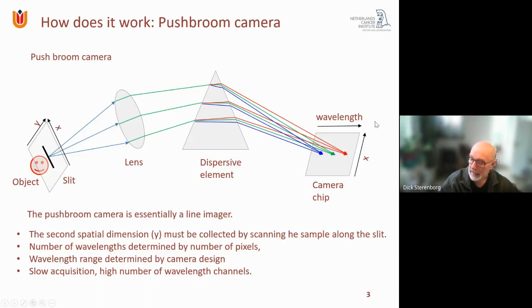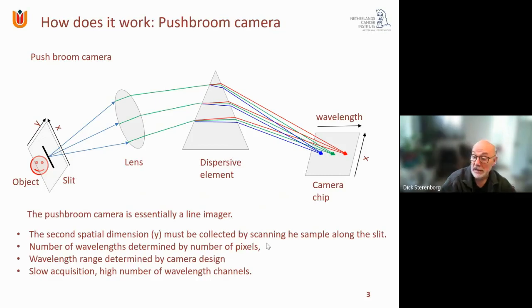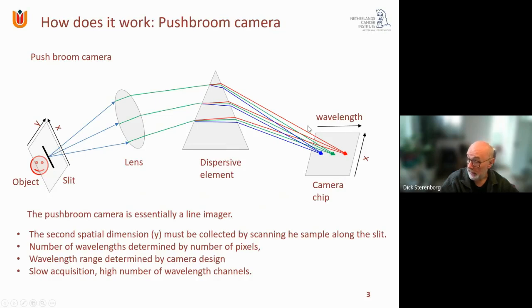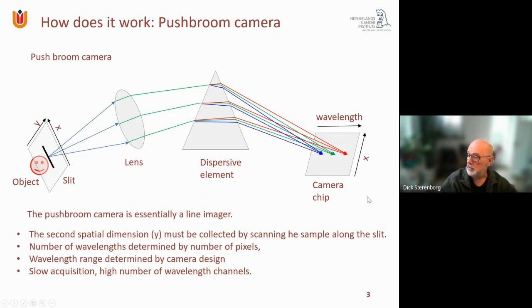The slit produces a line image: there is imaging in the x-direction for each wavelength, but not in the y-direction. The second spatial dimension is collected by scanning the sample. The number of wavelengths is determined by the number of pixels in the wavelength direction — easily hundreds — and the wavelength range is determined by the dispersive element and the sensitivity of the camera chip.